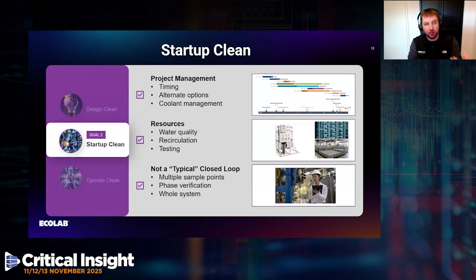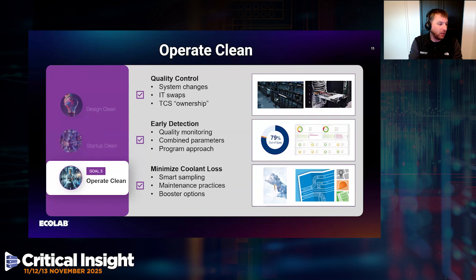It is important to do phase verification of the system when you employ it and hook it up and start it up, and that you consider the whole system and all its nooks and crannies when considering the cleanliness. Also, in terms of quality control during operation, it is important to consider what happens there. So what we see is customers exchanging blades because of lifetime, because of other concerns. So IT swaps, equipment swaps. And then the question often arises, who owns the loop and who owns the liquid that is inside these loops? This gets more tricky when you are a co-locating facility and your end customer is managing part of these tasks or equipment. So you must consider that in a good operation environment.